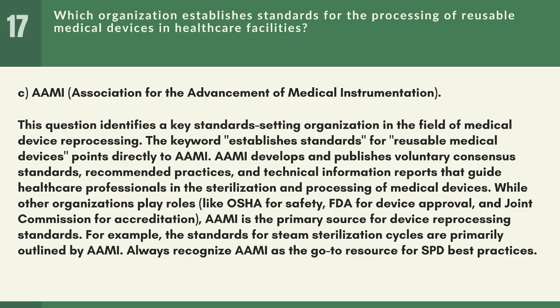While other organizations play roles, like OSHA for safety, FDA for device approval, and Joint Commission for accreditation, AAMI is the primary source for device reprocessing standards. For example, the standards for steam sterilization cycles are primarily outlined by AAMI. Always recognize AAMI as the go-to resource for SPD best practices.